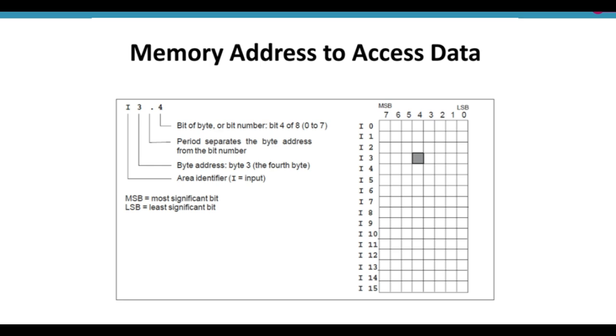If you want to address this bit 4, then its address will be I3.4, meaning byte number 3 and bit number 4. It can be written in this way: I3.4. I is the area identifier for the PLC input, 3 is the byte address, and 4 is the bit number.